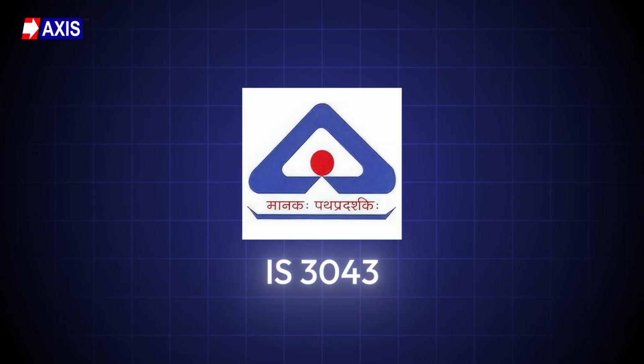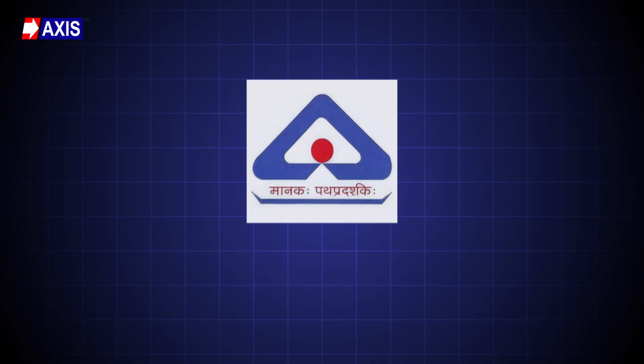IS 3043. This is the main Indian standard for earthing. It explains how to design, install, and test earthing systems for electrical installations. It covers soil resistivity, electrode sizing, conductor selection, and testing methods. IS 1772. This standard specifies the material requirements for copper alloy earth rods and plates for earthing. It defines the material properties, dimensions, mechanical strength, and electrical conductivity that your earth rods must meet for ensuring electrical safety.